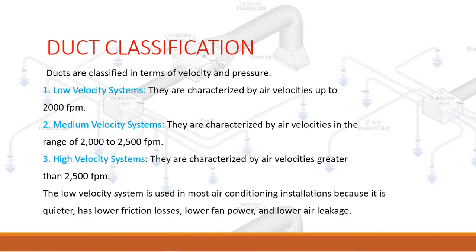Duct classification. Ducts are classified in terms of velocity and pressure. One: low velocity systems, characterized by air velocities up to 2000 FPM. Two: medium velocity systems, characterized by air velocities in the range of 2000 to 2500 FPM. Three: high velocity systems, characterized by air velocities greater than 2500 FPM.